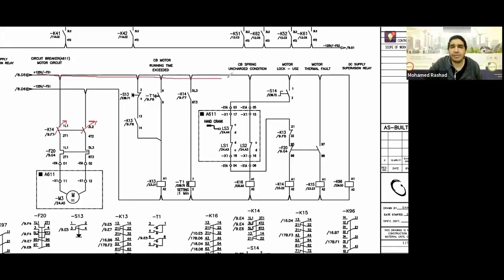So again, you have the positive passing through here from above. You have set the fuse, so this one closes, allowing the positive to pass here. You have closed your cover box or box cover to ensure you don't operate manually or insert your handle. This means you are not working manually or do not intend to work manually. As soon as you open the box, it is not possible. It allows the motor to turn.